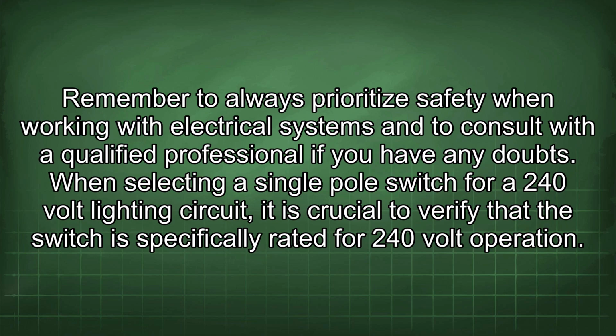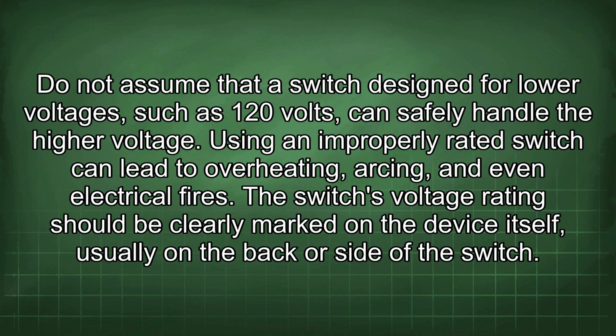When selecting a single-pole switch for a 240-volt lighting circuit, it is crucial to verify that the switch is specifically rated for 240-volt operation. Do not assume that a switch designed for lower voltages, such as 120 volts, can safely handle the higher voltage. Using an improperly rated switch can lead to overheating, arcing, and even electrical fires. The switch's voltage rating should be clearly marked on the device itself, usually on the back or side of the switch.